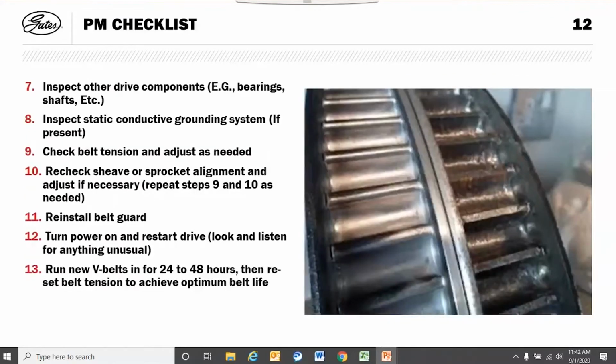So this one also, you can wear out a sprocket by having the belt too loose. It'll start over time. It'll run those teeth down so they wear off. Some of these are going to say that you should rub your hand across there. I don't recommend that because you can make those sprocket teeth so pointed that it'll actually cut you. And this will wear out the synchronous belt and reduce the tension.